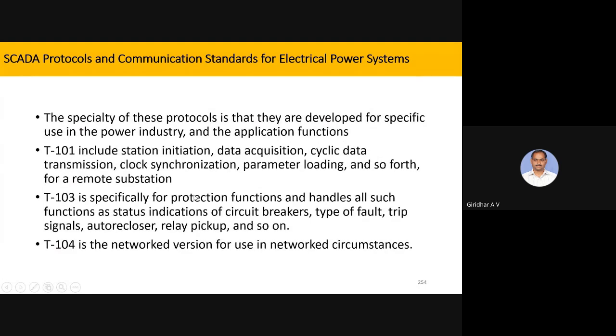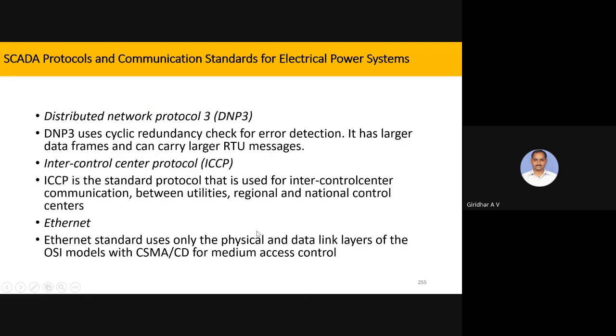Likewise, suppose if you see 101: station initiation, data acquisition, cyclic transmission. 103 handles the protection functions: circuit breaker, type of fault, trip signals. So in that way, it will be added in the protocols, how it can be performed. It can be taken care of, like network version.